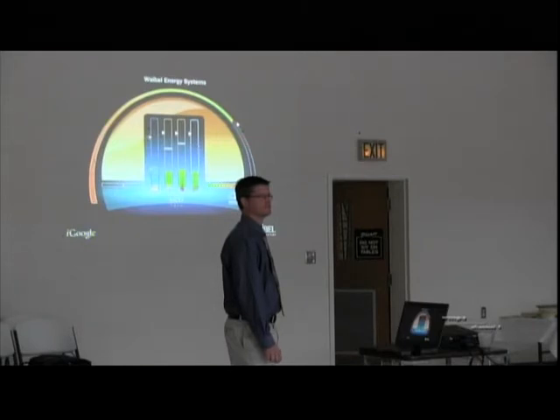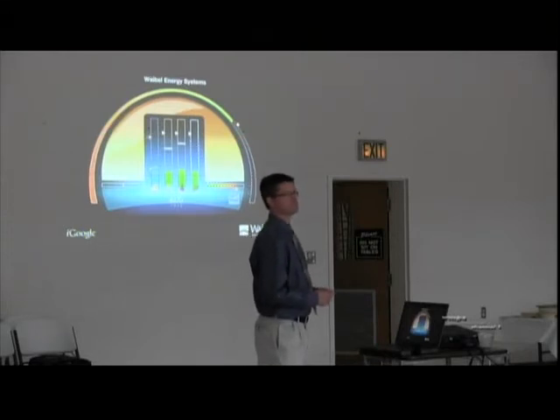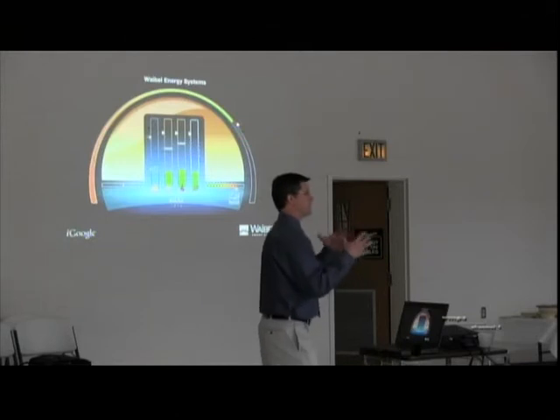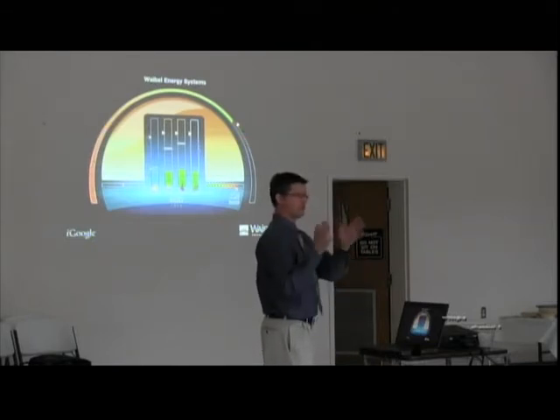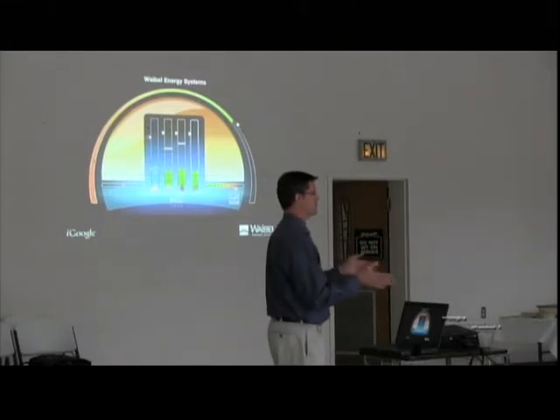So, we're using all the electricity meters, and we're comparing them against each other. We've sat in meetings and shown, hey, we made this adjustment to the system, and now we see this section of the building's energy use was here, now it's here. This energy use seems to be high on a weekend. Why is that? Are there gym lights being left on that aren't supposed to be on, and things like that. That's a really good example because we had enough metering and enough monitoring of this building that the gym lights were actually being turned on from dawn to dusk, and through the energy monitoring that we implemented, we were able to determine, hey, this is costing the school district so much money. Let's turn those lights off.